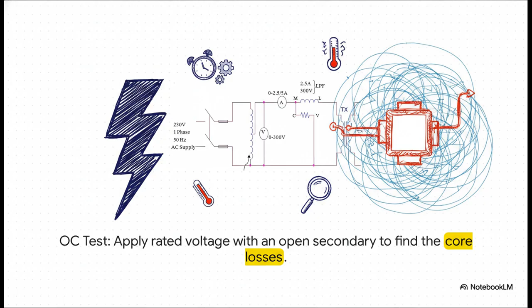Now for the pedal to the metal part. When the transformer is actually doing work, delivering current, a totally different kind of loss takes over: copper loss. This is just the heat that's generated by the current flowing through the resistance of the copper windings. The more work it does, the hotter it gets, and the higher the copper losses.